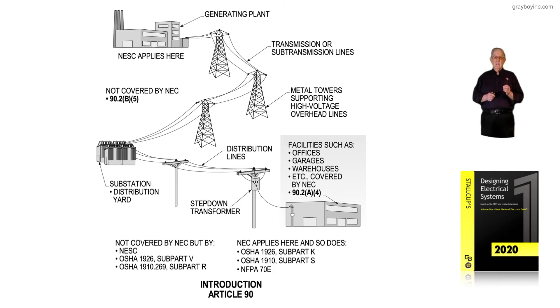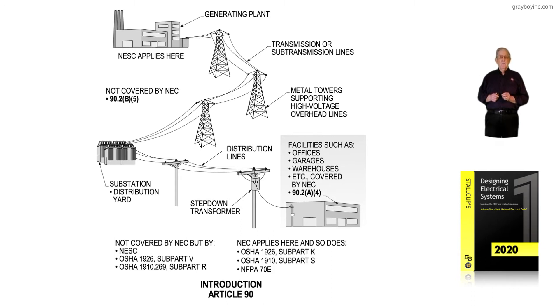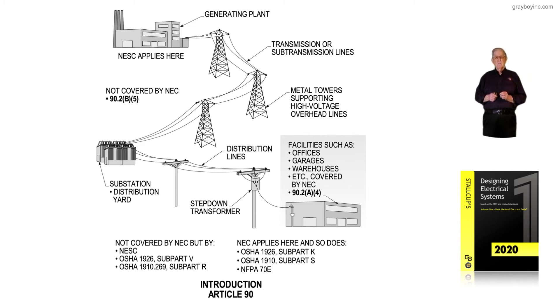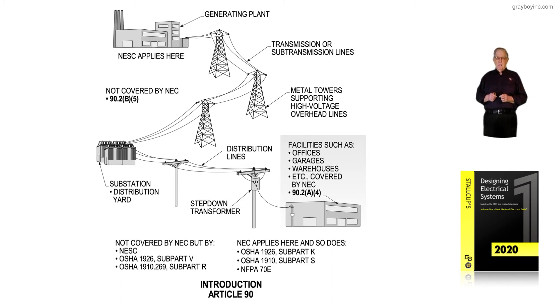The supply side is not covered by the NEC but by three standards. First, the National Electrical Safety Code covers the supply voltage. During construction of the generating plant, towers, transmission lines, substation, and distribution lines using utility poles, OSHA 1926 subpart V applies. Once construction has been accepted by the utility, OSHA 1910.269 subpart R applies. Those are the three main standards for the supply side.